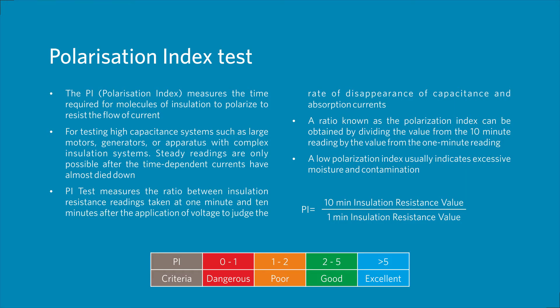Polarization Index Test: The PI, or Polarization Index, measures the time required for molecules of insulation to polarize to resist the flow of current. For testing high-capacitance systems such as large motors, generators, or apparatus with complex insulation systems, steady readings are only possible after the time-dependent currents have almost died down. PI test measures the ratio between insulation resistance readings taken at 1 minute and 10 minutes after the application of voltage, to judge the rate of disappearance of capacitance and absorption currents. A low polarization index usually indicates excessive moisture and contamination.